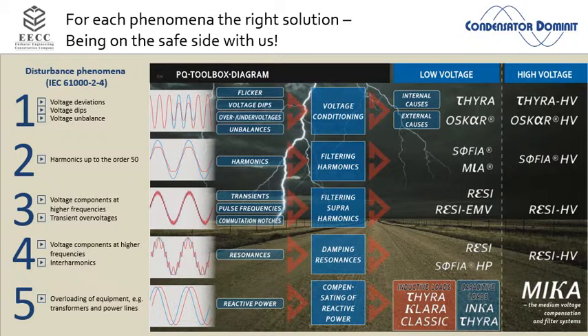If the voltage distortion by yourself is disturbing you, and you cannot allocate it to one single source like one machine, then I rather would go for a voltage control system. So in one case, I measure the current, I compensate the current. In the other case, I measure the voltage distortion, I put a filter on the bus bar system, and I just correct the harmonics for the whole factory. That's the only thing I will ask you: do we have to compensate one particular piece of equipment, or do we have to compensate a whole factory?